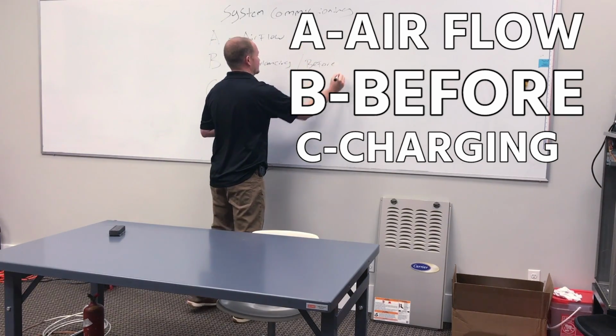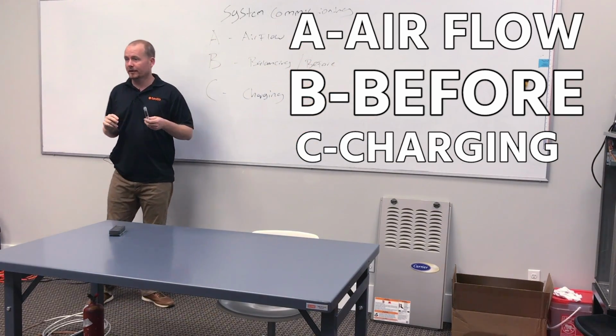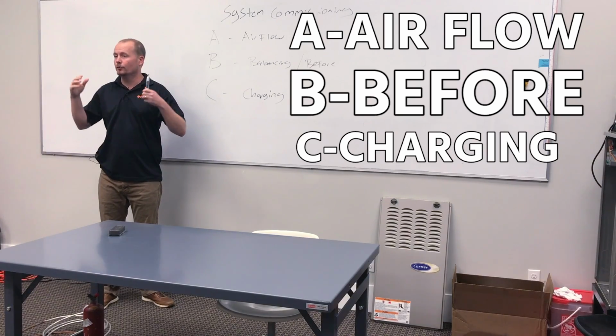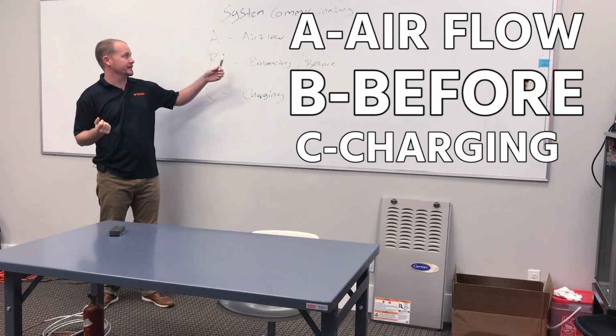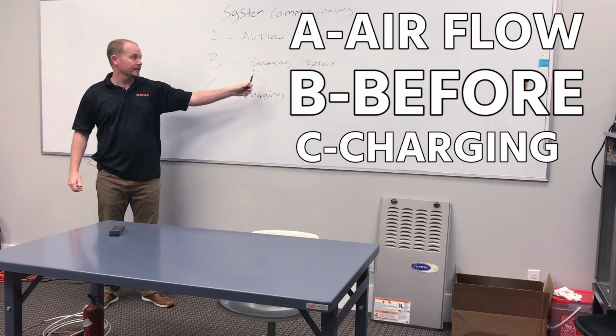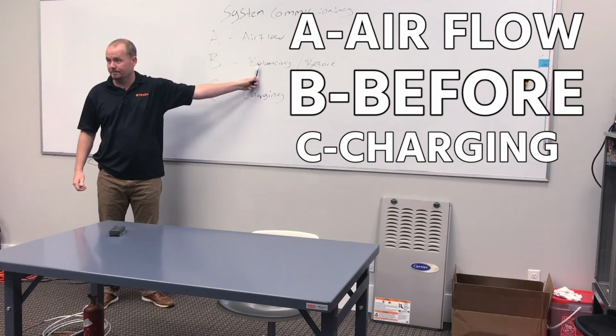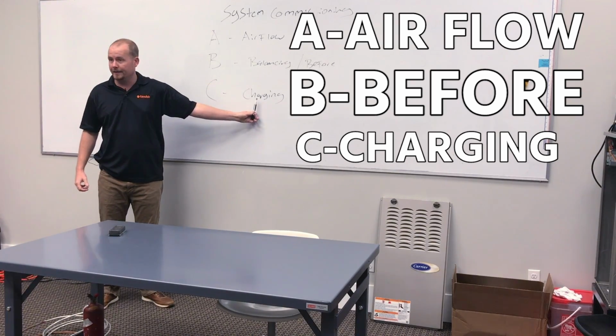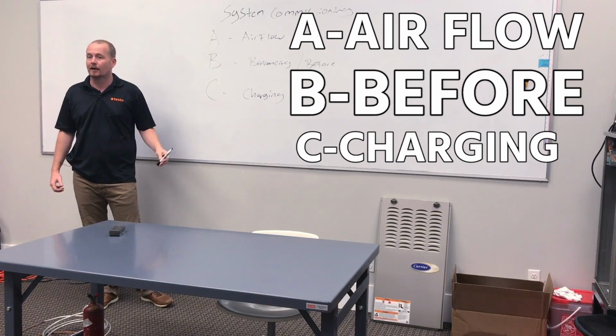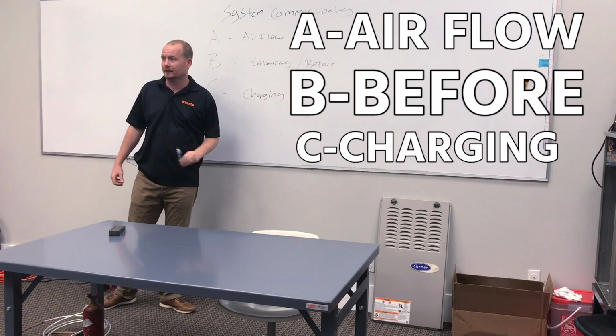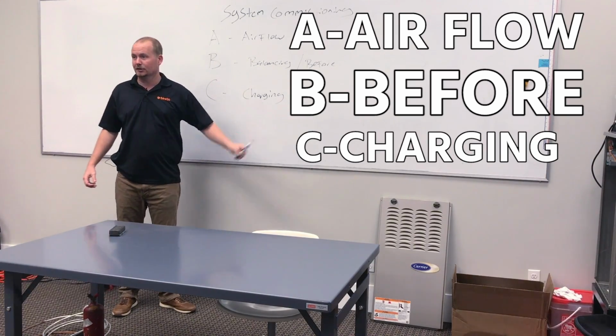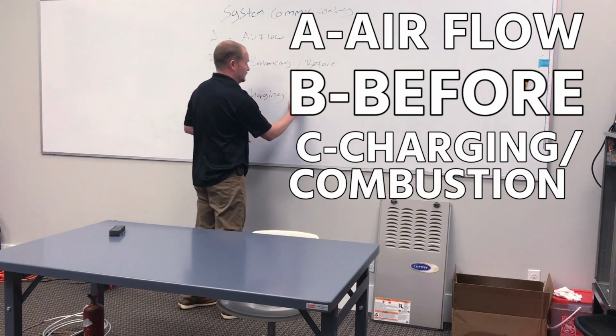Either way, if you want to be really thorough when you set up a new house or a new system, you should set your system airflow, then set your air balancing to make sure that you're putting the air in the right places, and then do your charging. That's the proper way to commission a piece of equipment. Or if you're working in a combustion heavy environment, sometimes instead of saying charging, they'll say combustion. So airflow, balancing, combustion. And maybe you could put combustion down here.